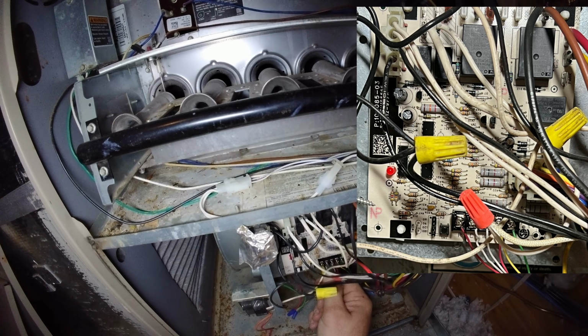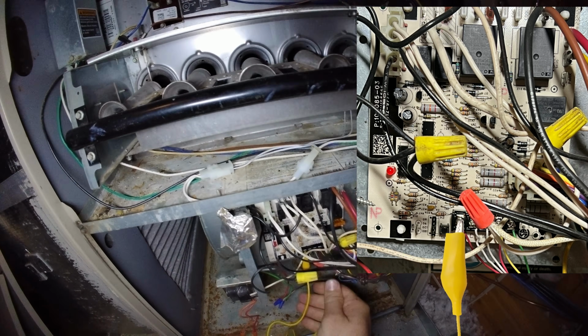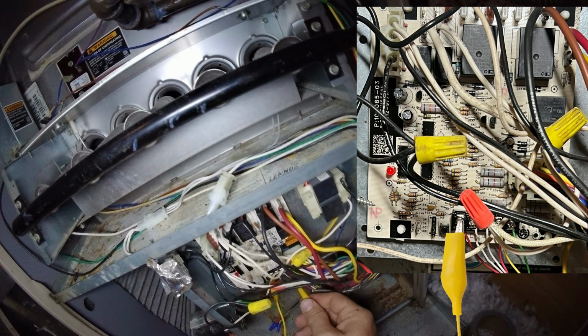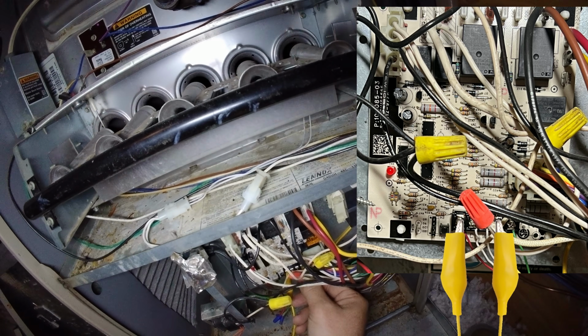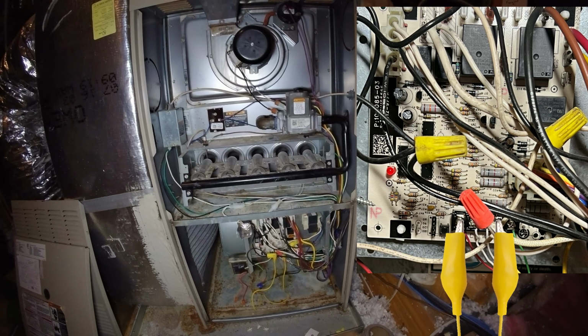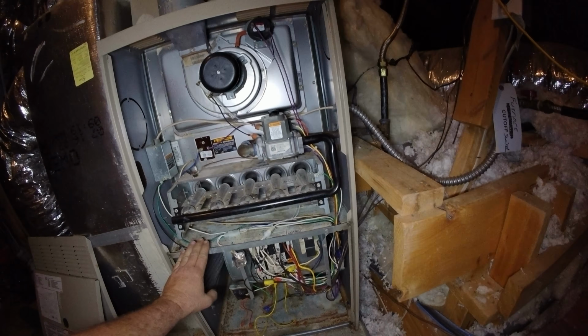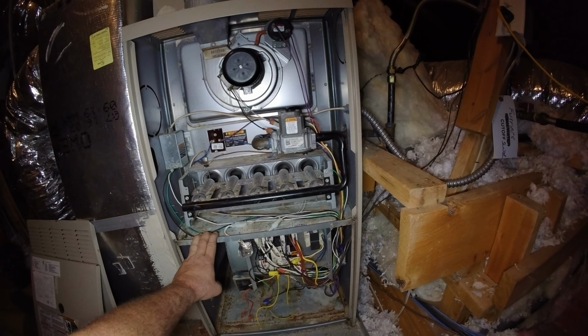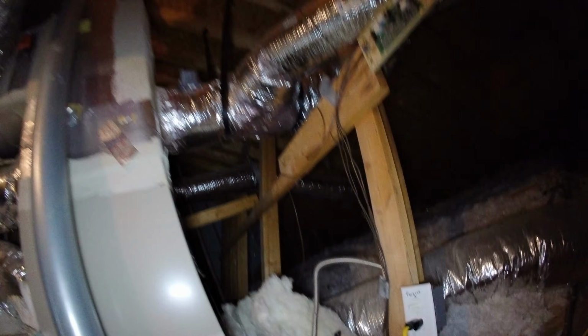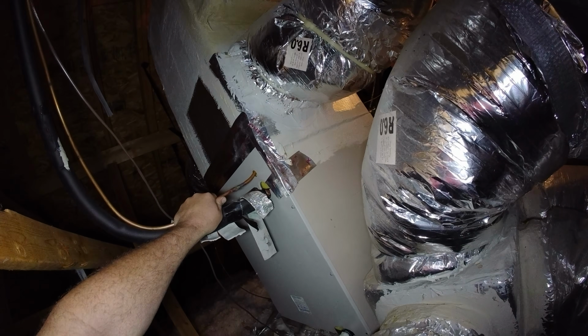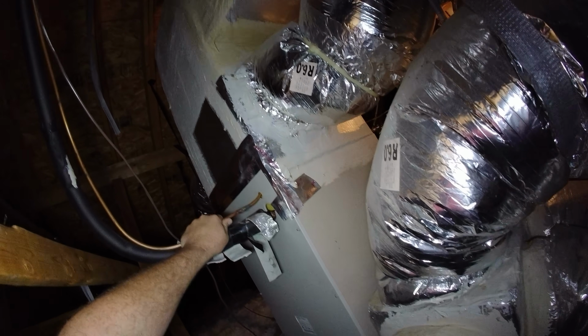by once again, if I can get it on there, jumping between our red 24 volt hot and our Y for the outdoor unit. And this time around we have not browned out on a call for cooling. It is going to energize this guy and our outdoor compressor. And naturally over here it's on the other side. So I do feel our compressor running outside, so I believe we are good to go on this one.